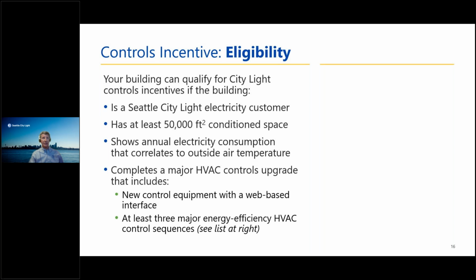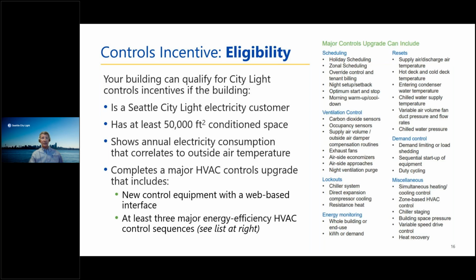And the other thing that's really important is you have to be looking to implement at least 3 major energy efficiency HVAC control sequences. So you're going beyond just a control system that schedules the building and provides basic settings, like heating to 72 in the winter and cooling to 74 in the summer. You have to have sequences that provide better flexibility around scheduling, resets for supply air and return air, and lockouts.